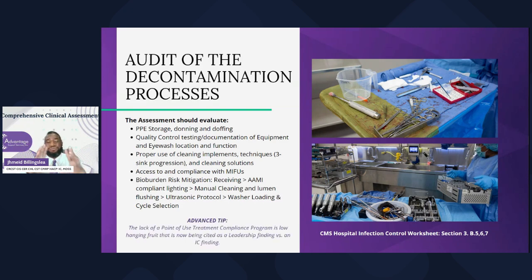Advanced tip: the point of use treatment compliance program. That means, am I rating, not just using my camera to take pictures of the bloodiest, dirtiest stuff, but am I rating compliance with all the things? No sharps, delicate on top of heavy, the case cart properly marked as clean versus dirty, all those elements.